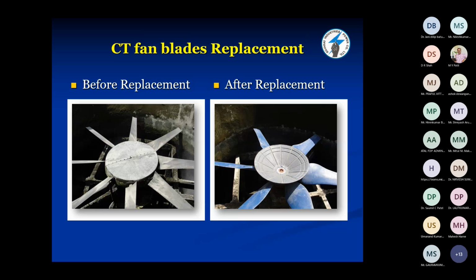This is the picture of cooling tower fan blades. Before the replacement, this type of fan was there. This is the FRP blade, it's simple, original. And now we have replaced it with this aerodynamic shape cooling tower fan, the modified design. By fitting this type of fan, each fan is having a 7 kilowatt power saving.